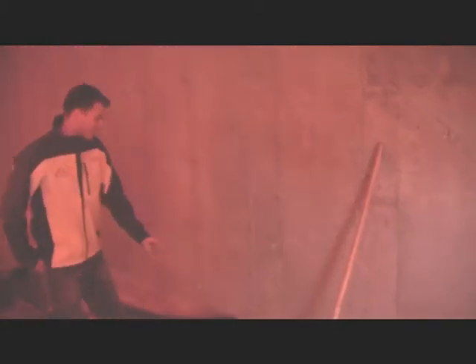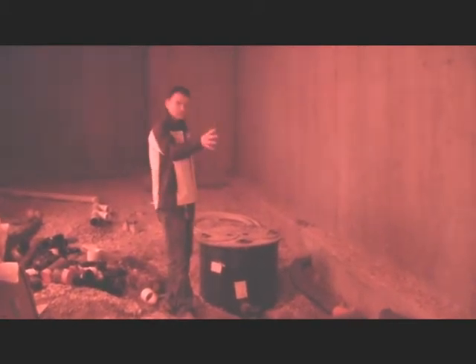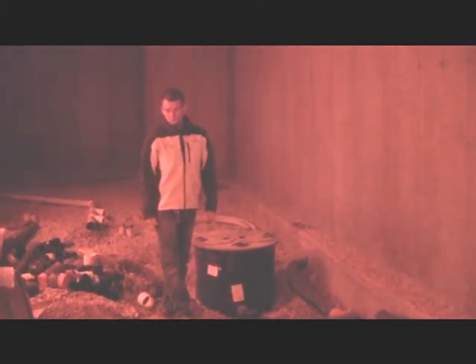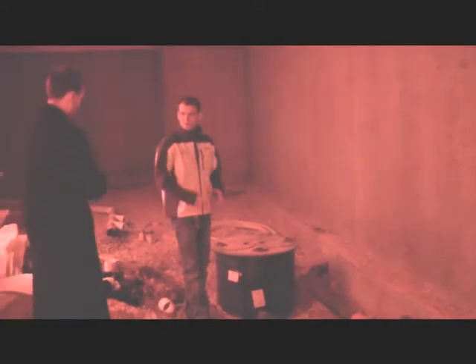One of the things we've done with the outside is we've taken our downpipes from the roof and hard-piped them into the basement here, and they spill into this rain barrel. In this rain barrel we'll have one main pump to pump out the excess water, and then a backup pump as well in case the first pump fails, so you don't suddenly have a flooded basement. All the outside excess water will go into this barrel, be pumped out, and into the storm sewer, keeping everything on the outside as clean and streamlined as possible.